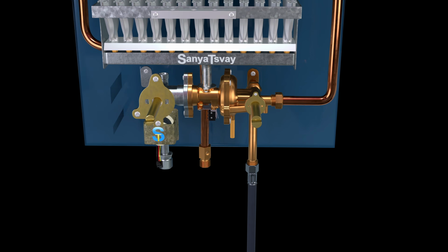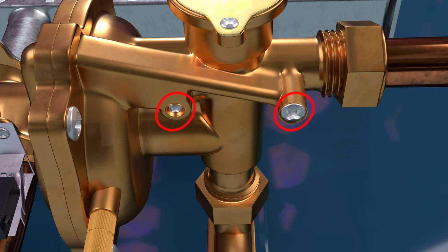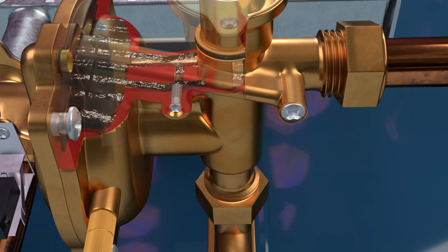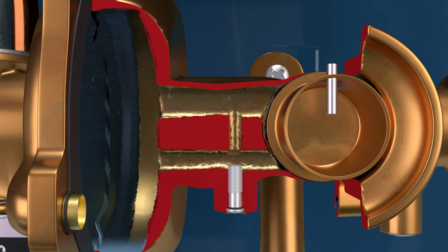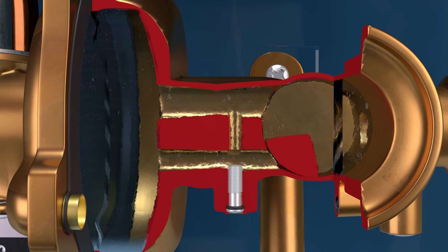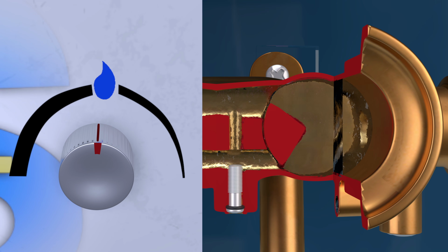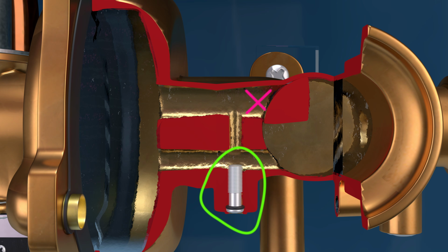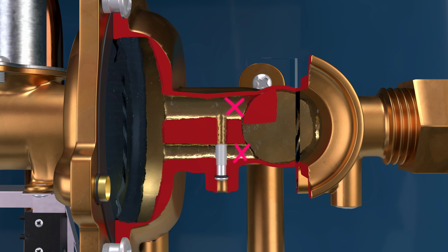To conclude, I want to talk about the two adjustment screws located on the right side of the water block. I'll say this right away. You should not touch them, as they are factory set. Everything that follows is provided only to help you understand how the system works. The small screw is located in an auxiliary channel that leads into the flow regulator. It does not bypass the valve. It works only when the main channel is almost closed. In other words, at maximum flow, this screw has no effect. But when the water flow is reduced to minimum, it is the one that determines what minimum flow will still be able to enter the heat exchanger. Under no circumstances should this screw be fully tightened. Otherwise, there is a risk of overheating the heater with no water in the heat exchanger.